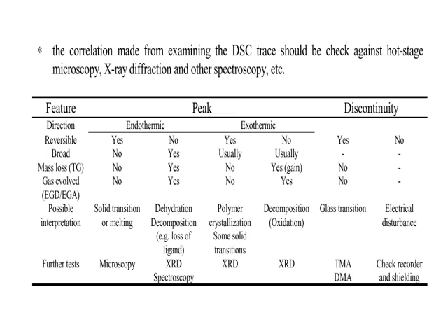The conclusions drawn from a DSC trace should probably be corroborated with some other technique. You can try to figure out this table. I think it's self-explanatory. If you have a melting event, something like hot stage microscopy could be used to actually observe that melting event occurring at a particular temperature. If you have dehydration or decomposition, you might be able to check it with X-ray diffraction. If you've crystallized something or actually changed the structure of it, so maybe you've gone from one crystal type to another crystal type, X-ray diffraction could be used to check that, and so forth. I think this slide is fairly self-explanatory.